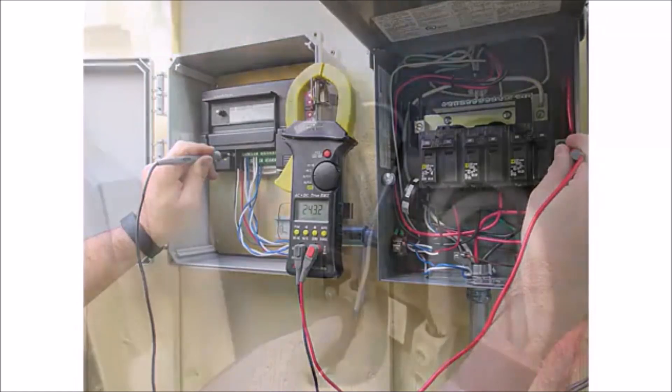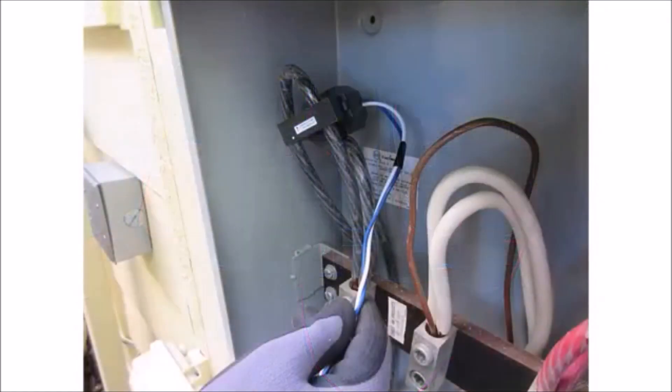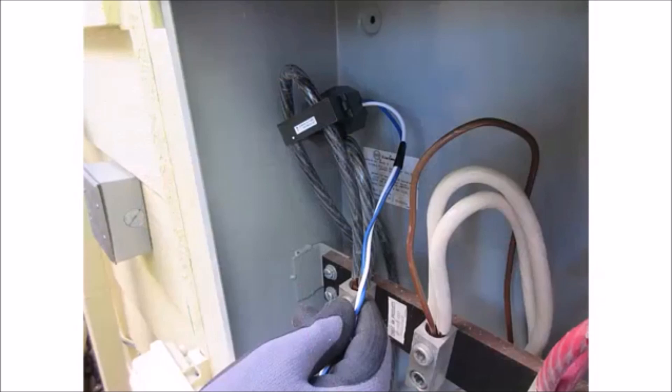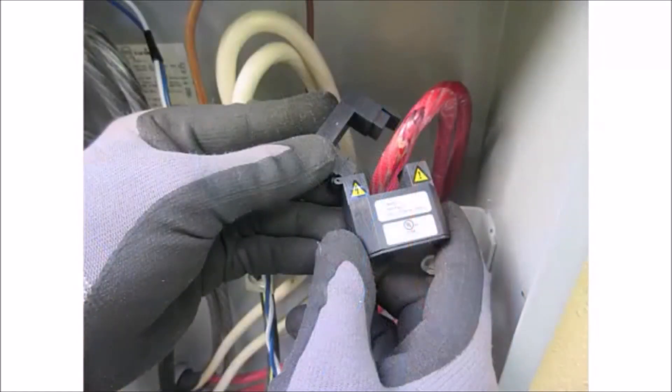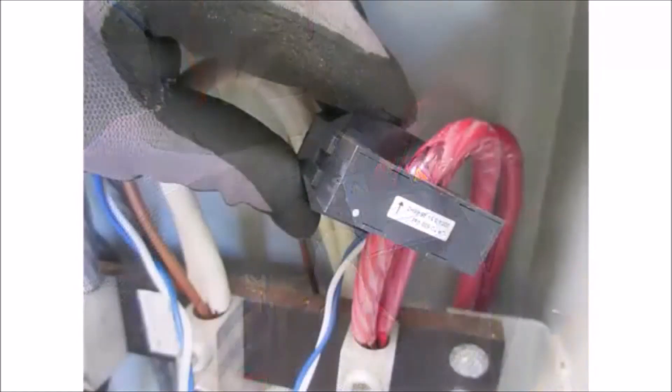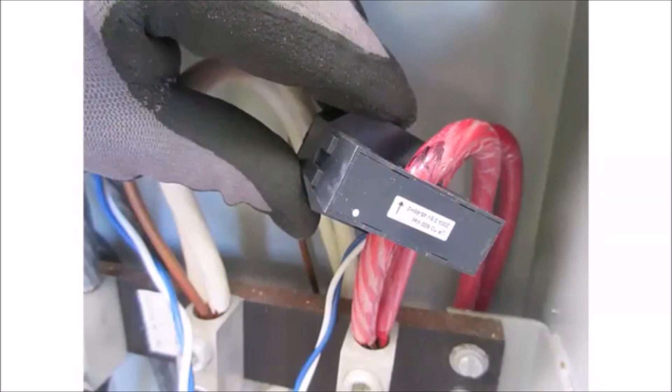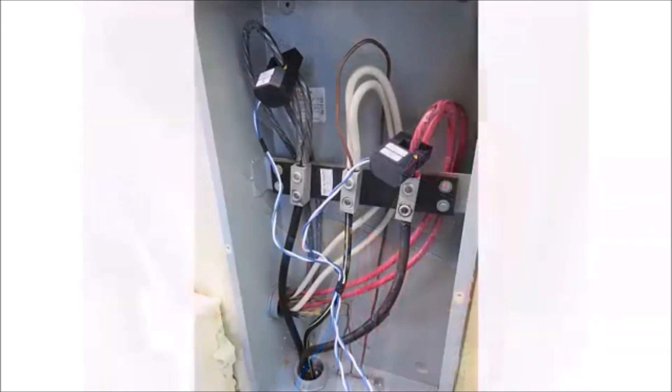Install the marked CT on the main service conductor line 1 with the CT arrow pointing toward the loads. Verify the CT is firmly latched. Install the unmarked CT on the load center feed wire line 2 with the CT arrow pointing toward the loads. Verify the CT is firmly latched.